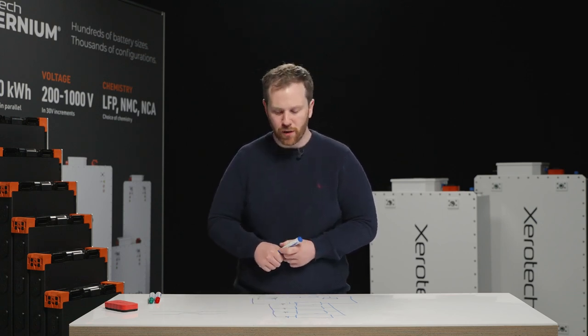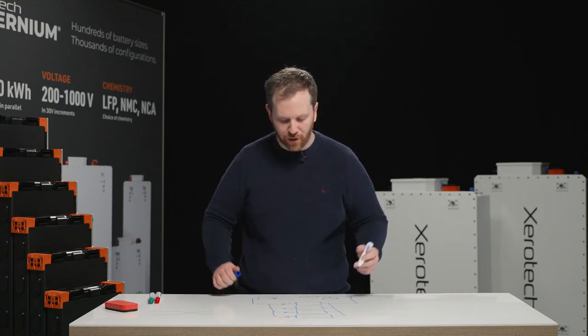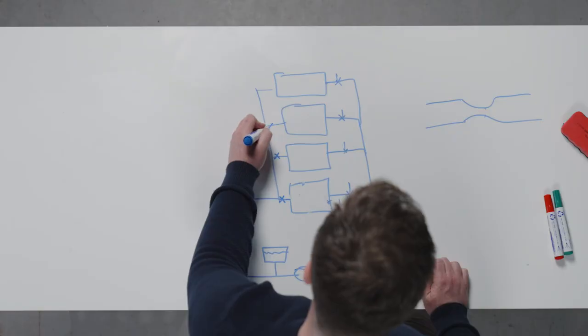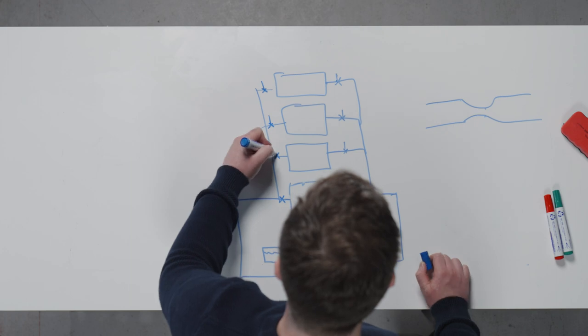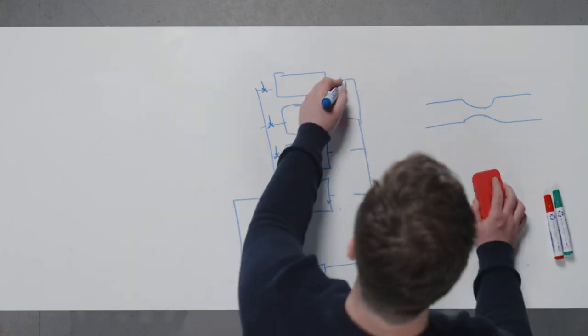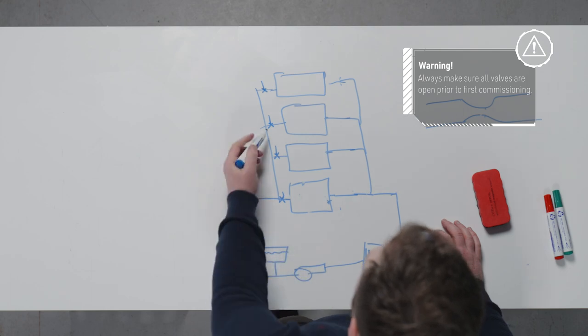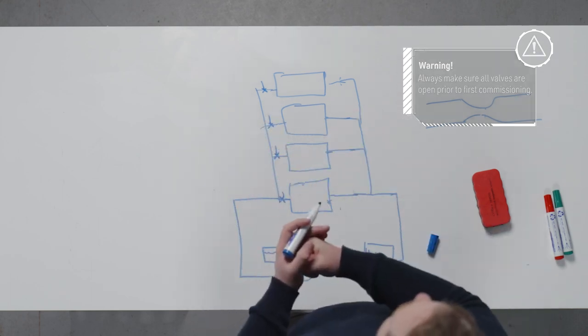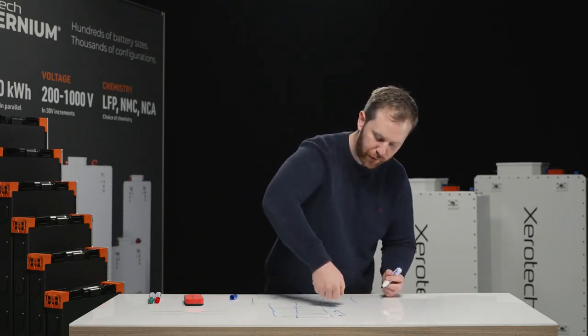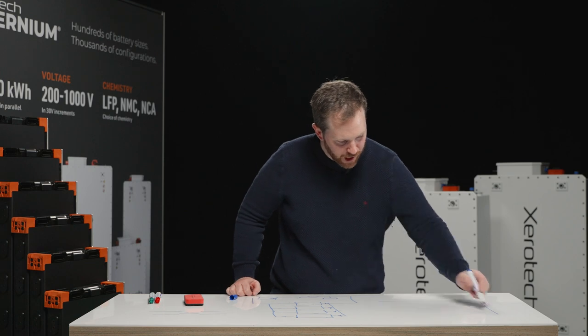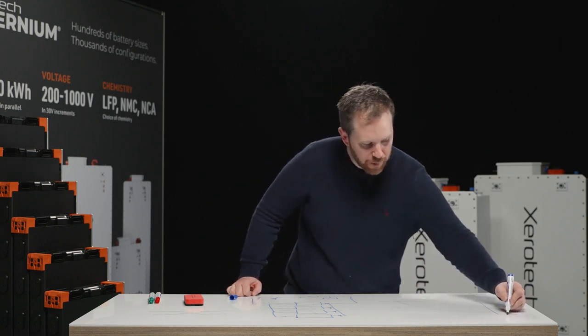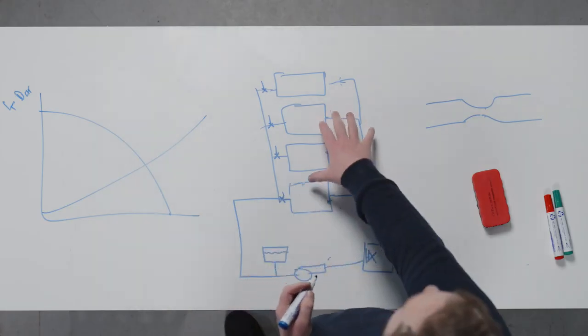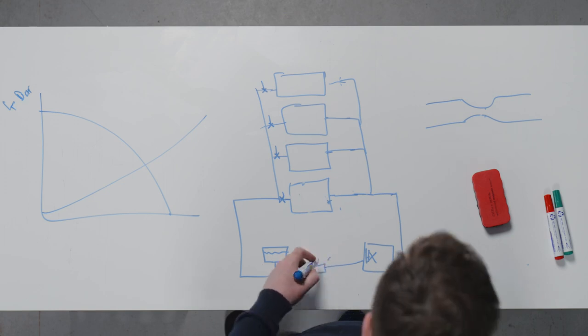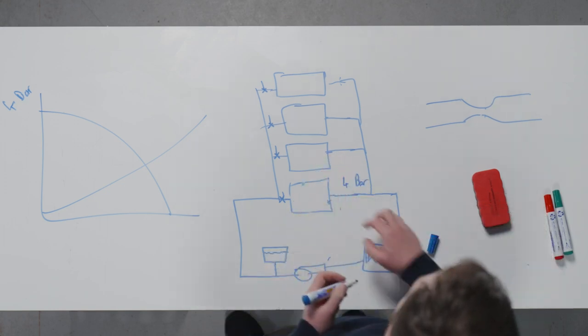So a big watch out to do here is, especially during the commissioning phases, that you don't accidentally have your balancing valves at the back of the pack, and when you're first commissioning it, that you actually forget to open all the valves. So if these are heavily constricted, in this ideal system, you could have massive pressure drop here because they're trying to go into a choked off flow. So as you're balancing this system, you might close all the valves fully, turn on your pump, and forget that your pump is a high capacity pump because it's got to pump hundreds of liters a minute through lots of big packs here. But you shut all your valves and you didn't realize that. So now you immediately develop 4 bar or some very high pressure on the inlet side of all the packs, and you can blow every pack in the system.